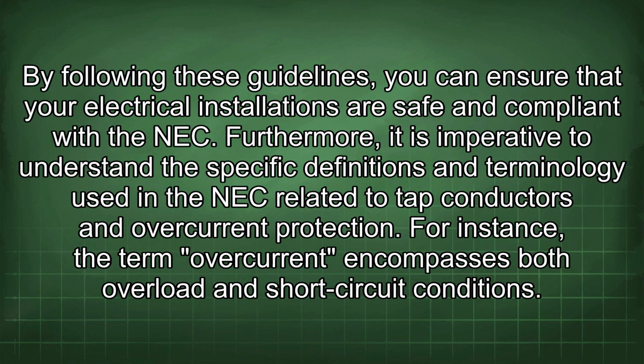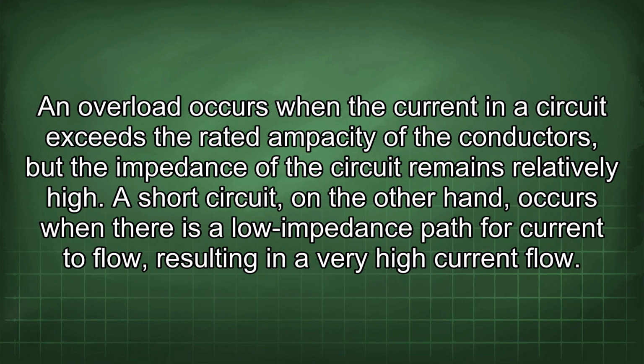By following these guidelines, you can ensure that your electrical installations are safe and compliant with the NEC. Furthermore, it is imperative to understand the specific definitions and terminology used in the NEC related to tap conductors and overcurrent protection. For instance, the term overcurrent encompasses both overload and short-circuit conditions. An overload occurs when the current in the circuit exceeds the rated ampacity of the conductors, but the impedance of the circuit remains relatively high.